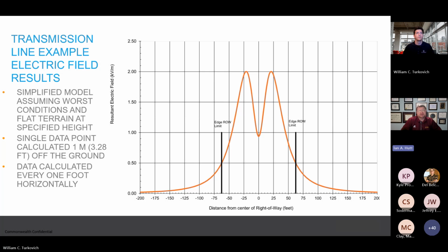And that seems arbitrary - like why pick 1 meter? That seems weird, why not 2 meters, or the height of a person? The convention is we pick 1 meter because generally, if you're going to reach out and touch something, for an average person of average height, that's usually around 1 meter off the ground. That might be a fence, like that earlier example, or a vehicle that's in the right of way or near the edge of it. We're really looking at where that induced voltage might be and where that touch potential may be - that's why we tend to focus at that height.